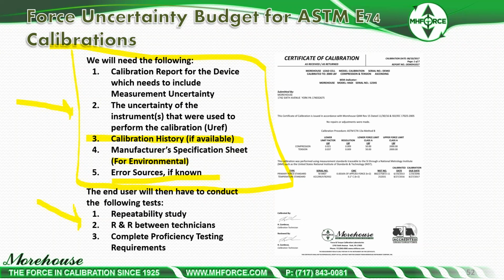So how do you know your measurements are as good as you say they are? The only way to prove it is through proficiency testing or doing an ILC. So the best thing is, if you're out there and you're wondering if you're generating the appropriate amount of forces, you can absolutely call us. We could lend you a cell. We could calibrate a load cell in dead weight, send you the data, and you could do a comparison on your own to know if your system is good or not. That can be for force or torque.